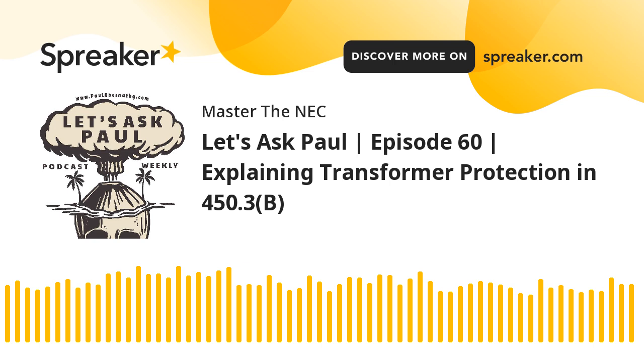Now, I'm going to give you a little tip. This is not exam prep. This is just a tip. If there are any continuous loads taken into consideration in the panel that's being supplied by this transformer, make it easy on yourself. Again, this is not exam prep, because in an exam they'll tell you whether to consider these as continuous or not. In the real world, it's so much easier to take the conductors on the primary of that transformer, and if there are any loads supplied by that transformer that are going to be rated as continuous, and you're liable to have them, whether it's lighting loads in a commercial building, for example, and the code dictates they're continuous loads, then the easiest thing you can do, to make life simple, is size it as a continuously loaded transformer. So just take the values of that transformer line current at 125% and size the conductors accordingly. I'm just saying, make your life easy.